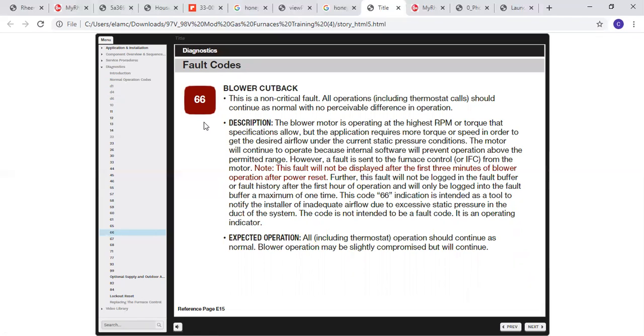Had one where they had half the vents cut off in their house, and this 66 popped up. Now I knew the duct system, so I knew the static pressure was fine. So when we got this 66 code, I knew something was wrong. So we just had to kind of dig in a little bit, and they had shut all the vents on the second floor. Expected operation, if you get the 66, it will actually disappear after a short period of time. That 66 is just kind of a tool to tell you.